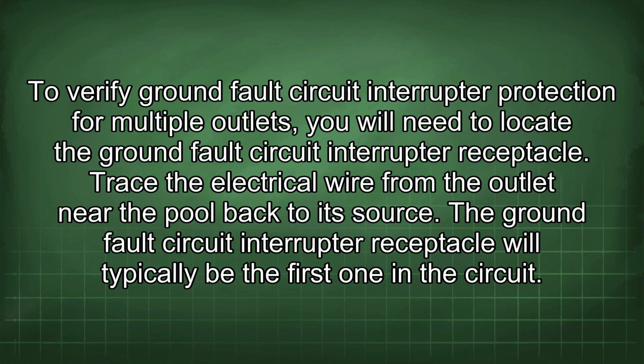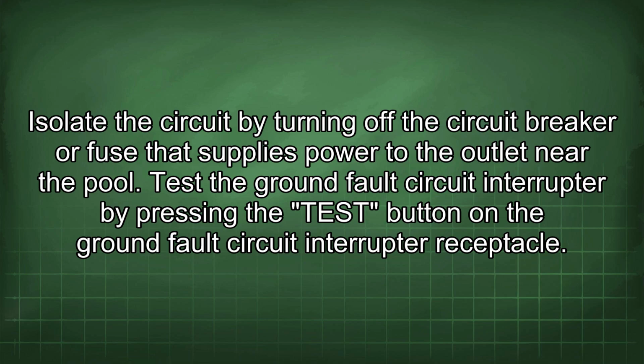To verify ground fault circuit interrupter protection for multiple outlets, you will need to locate the ground fault circuit interrupter receptacle. Trace the electrical wire from the outlet near the pool back to its source. The ground fault circuit interrupter receptacle will typically be the first one in the circuit. Isolate the circuit by turning off the circuit breaker or fuse that supplies power to the outlet near the pool. Test the ground fault circuit interrupter by pressing the test button on the ground fault circuit interrupter receptacle.